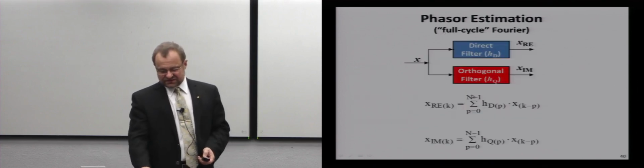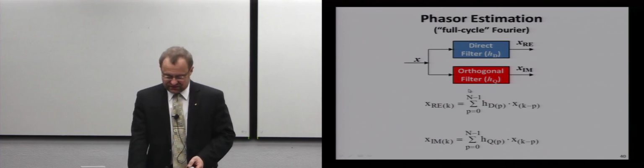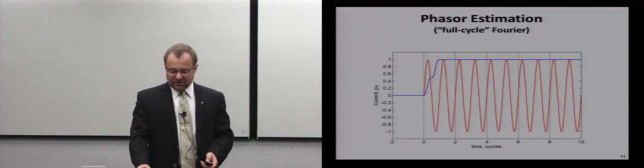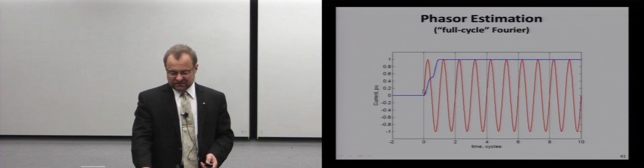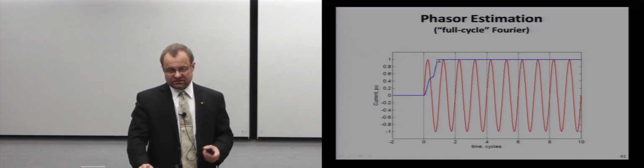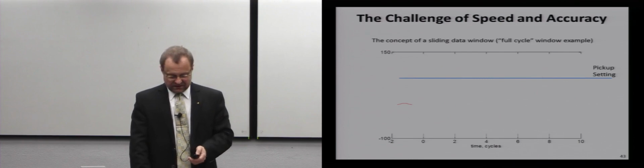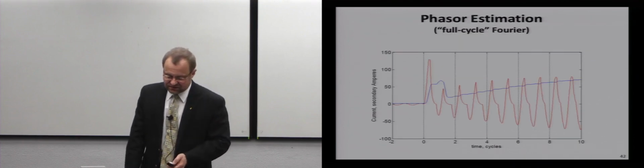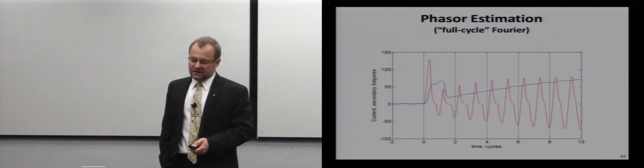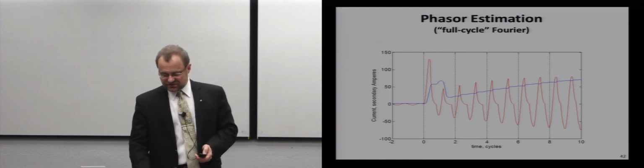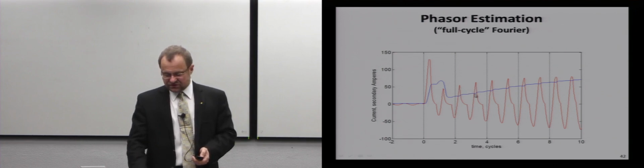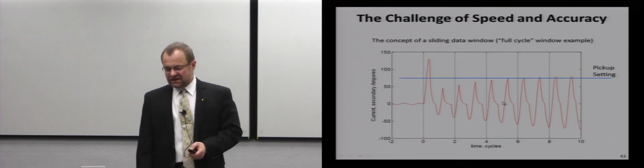I could go on and make the full cycle algorithm right now. So I use 16 milliseconds of data. So now it will take me 16 milliseconds to make a full transition between old value and new value. So if my pickup setting was here, I don't care, I will still trip very fast, right? But if my pickup setting was here, it will take me 16 milliseconds to realize that the value is above the pickup, right? So this is how it responds to that distorted waveform. It's not bad. Here the error is because of CT saturation, unfortunately. That's not the fault of the algorithm. That's the function of that distortion which came from saturated CTs.